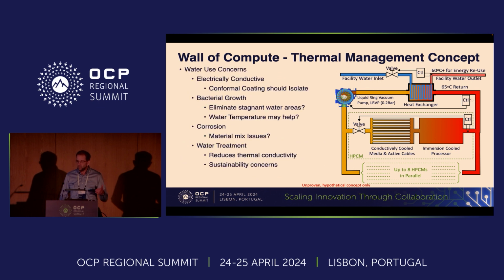Looking at the water side of things, we've identified that water use concerns are big. It's electrically conductive - I mentioned the conformal coating which should isolate us. We've got this bacterial growth challenge. We understand stagnant water areas cause a big problem, so could we design this to eliminate stagnant water areas? The water temperature today is in a beautiful range for bacteria to grow aggressively, so will hotter water improve that, or will it just shift to different bacteria?